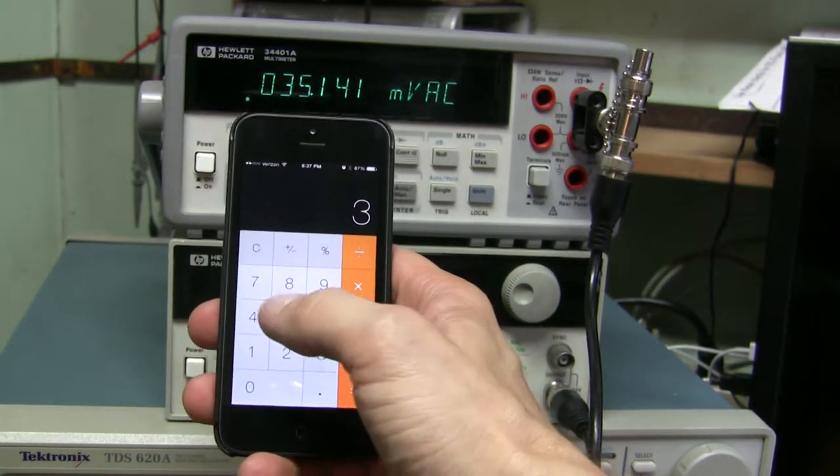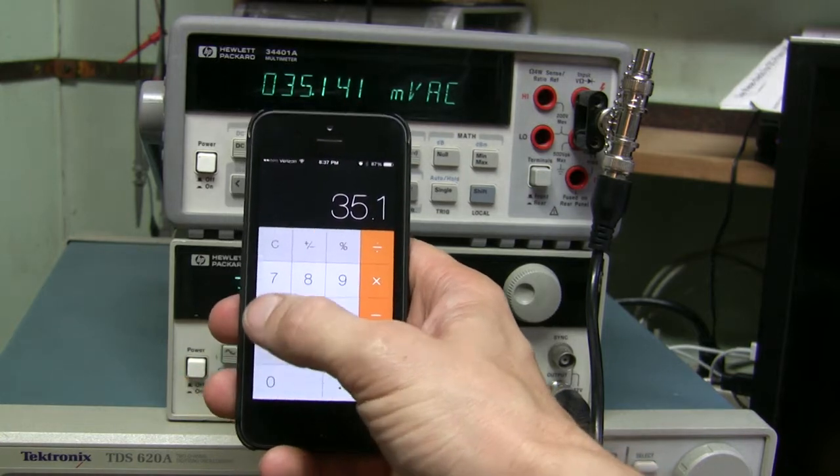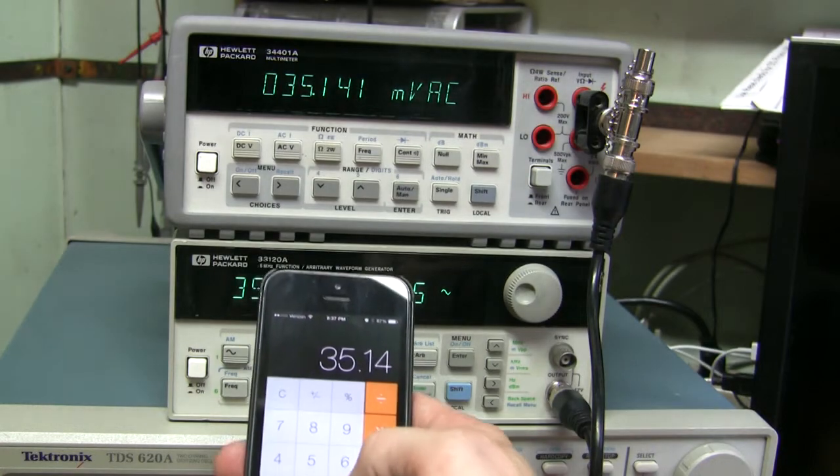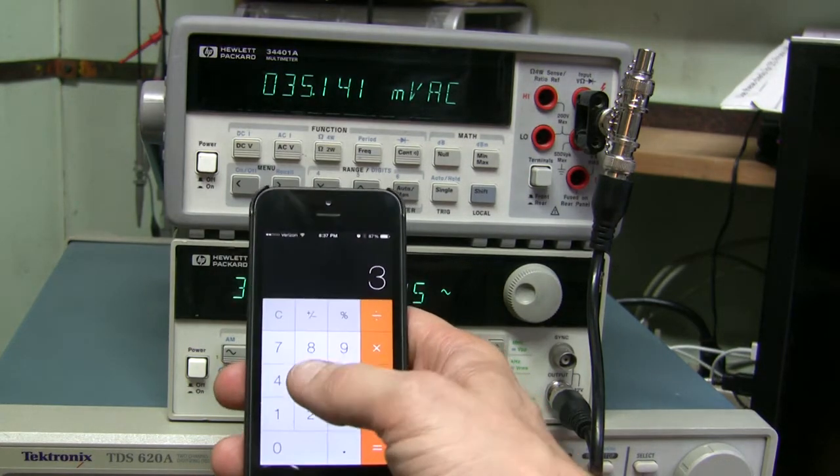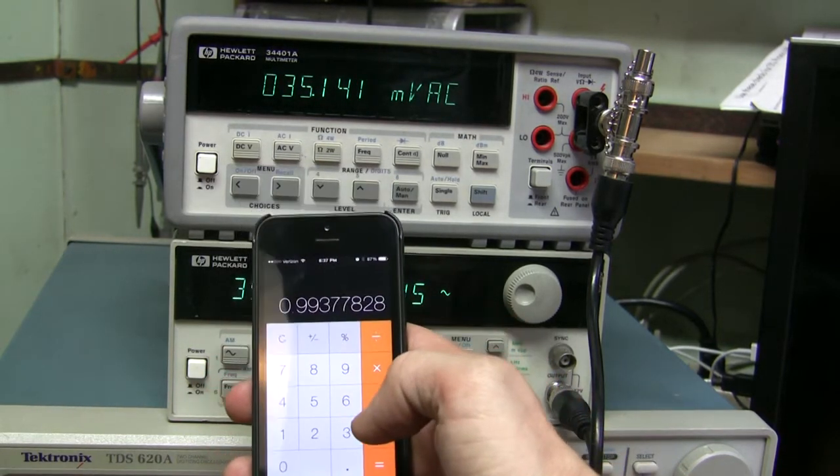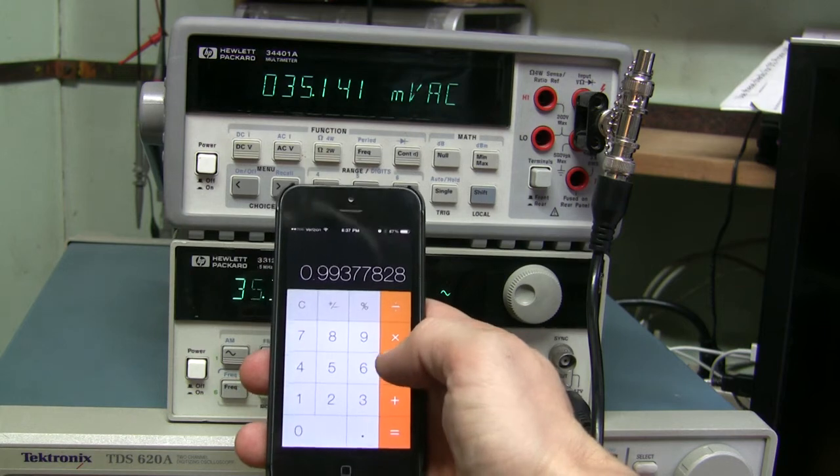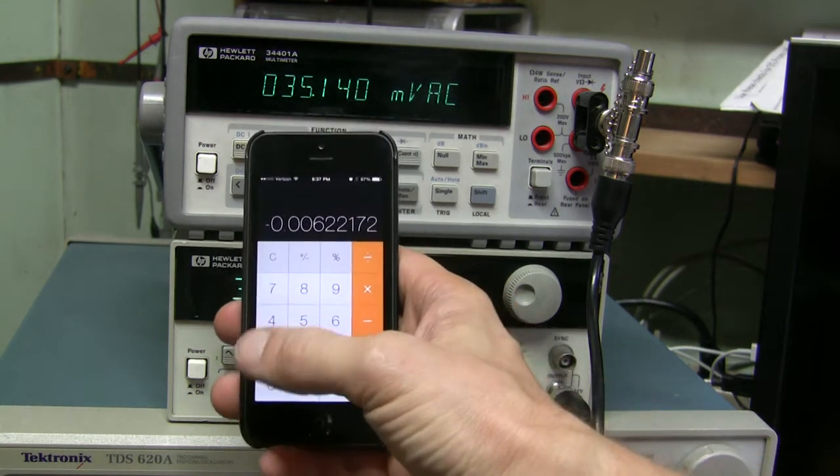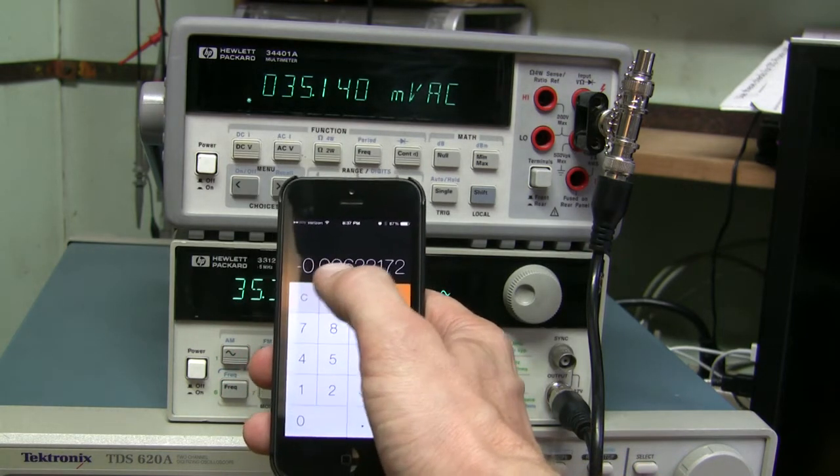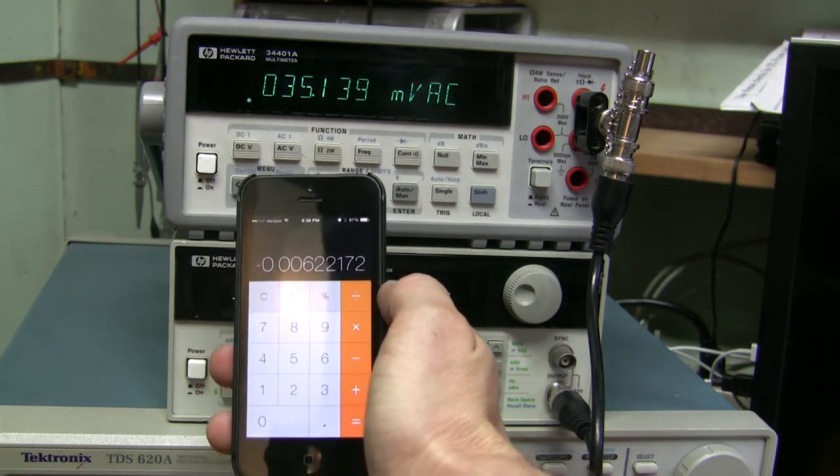Here we are. So first we enter what we read, which is 35.14 let's say, divided by 35.36 what we should get, and minus one. All right, so this is the difference. If we shift the point two decimal places, it's going to be 0.6 percent out, which is well within spec.